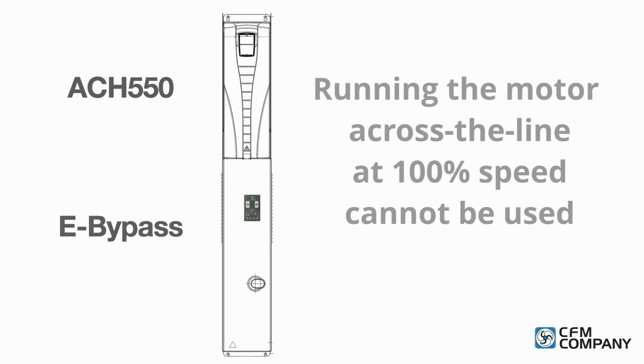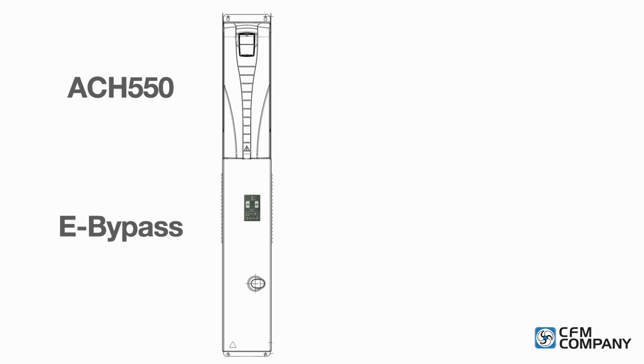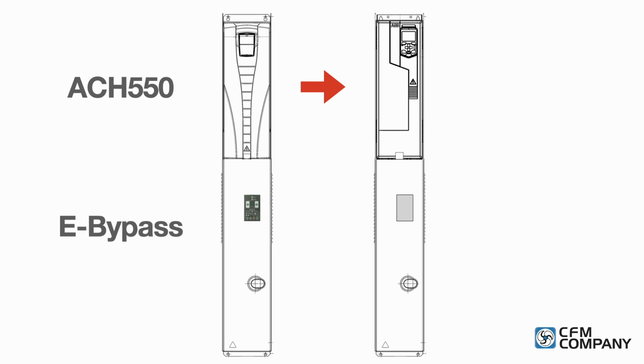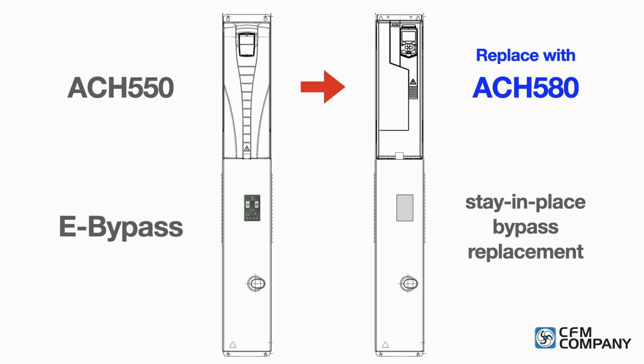For customers where the original drive included an electronic bypass and running the motor across the line at 100% speed cannot be used, a stay-in-place replacement should be considered. The customer can upgrade to a new ACH580 drive and reuse key components of the original enclosure. This will help to reduce installation costs and save money.